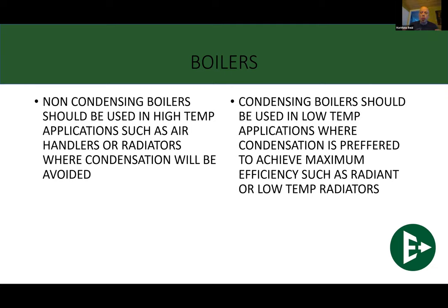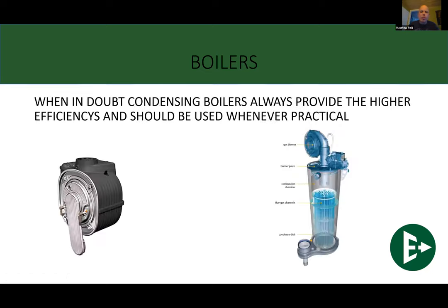That being said, if you're dealing with an indirect water heater that usually likes to see that nice hot temperature being supplied to it, somewhere around the 180 degree mark, you can use, in theory, either or. So whatever system you're working with, be sure to adjust and adapt for that indirect water heater if you're using one. Or play with the specs of that indirect. You can make an indirect create a ton of hot water by providing it 150 degree water and then returning it at 130. You're still within your condensing application. You just need to know that your hot water output is going to be less than 150 rather than what it would be at your industry standard of 180. So just things to keep in mind when we're designing a system as to what sort of maximum efficiencies you want to be playing with.